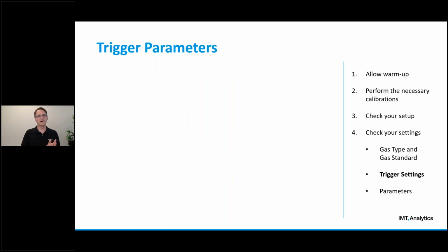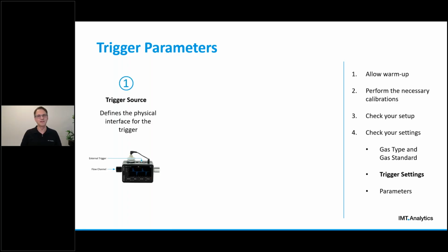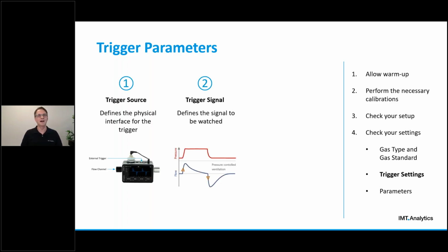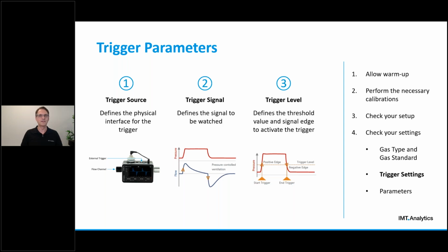Okay, before we talk about how we can determine suitable trigger settings, let's talk about some basics about trigger settings first. Trigger settings are typically defined by three main parameters: a trigger source, a trigger signal, and a trigger level. The trigger source defines the physical interface for the trigger. In this example, this could be a measurement in one of the flow channels of the device, but it could also be a pressure port of the analyzer. Most analyzers also offer the option to use an external digital trigger signal as trigger source.